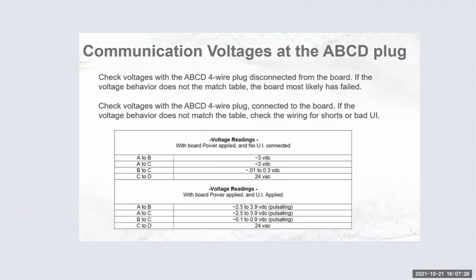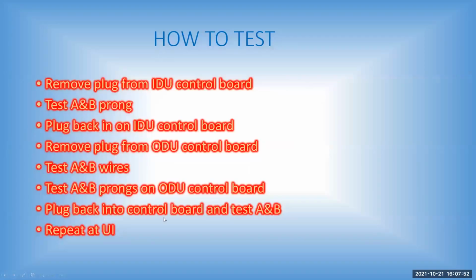This seems very threatening and difficult, troubleshooting a communication circuit. It's actually very easy once you do it a couple times and you understand what voltage you should have where and when. If you get on one and you're having problems, can't figure it out, give us a shout. If we have the time, we'll sit and walk through it with you and test it out with you. Very seldom is it due to a CD terminal issue. It's usually in your A and B where your communication is. C and D is your power back.